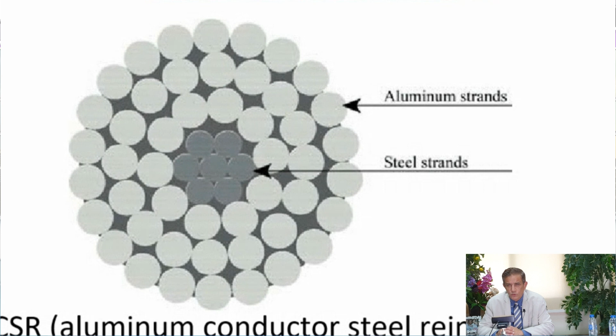Now we'll have a look at the line conductors. Normally, we said that we select aluminum as the conductor for transmission lines, being cheaper and lighter. But being lighter, it will be subjected to wind forces and tension strength, which aluminum cannot withstand. So AAAC, all aluminum alloy conductor, is used in some applications, but the most used one is the ACSR, aluminum conductor steel reinforced, where the aluminum strands are in the periphery of the conductor and in the center there are the steel strands. Normally the ratio between them is like 4:1, which means the aluminum strands are 4 times as much as the steel strands.